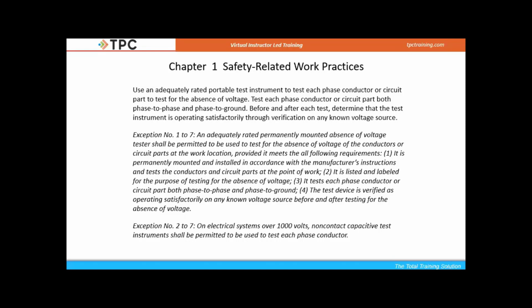Meter never moves. It's always right there. And usually it's in the form of some lights. We don't actually see a voltage reading on it. We just see some indicator lights. And so it is going to be UL listed and labeled for this purpose. It is going to do exactly what we would do, test each phase conductor, phase to phase or phase to ground. It is going to verify itself that it works before and after, and we will see a picture of that coming up on the next slide.